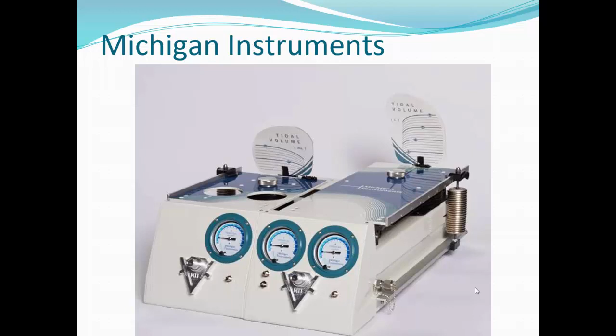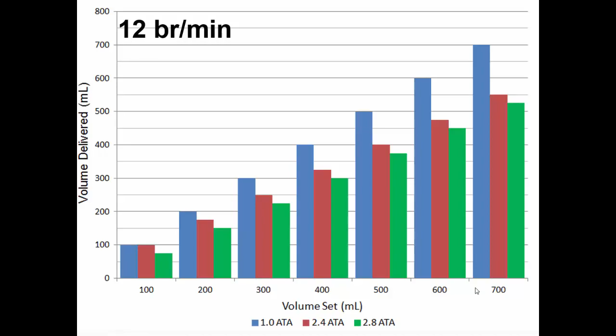Blue is sea level, and so you can see a nice correlation. You give 700 cc's at sea level, you get 700 cc's back. And then the red is 45 feet, green is 60 feet of seawater, and you can see a nice incremental decrease in the volumes exhaled versus volumes delivered, by a difference of about 100 cc's for your common ventilator settings between 400 and 500. And it's set at 12 breaths per minute.